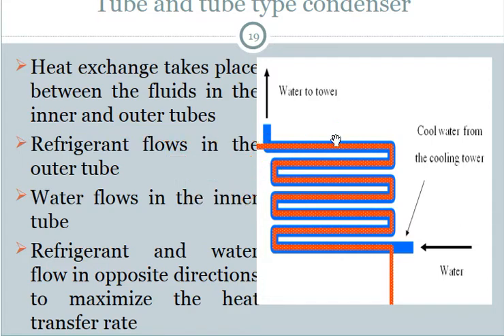The tube-in-tube type condenser follows the same spiral pattern for both the tube and shell. As seen in the figure, the red tube carries the refrigerant and the blue tube carries the water. Heat exchange takes place between the fluid in the inner and outer tubes. The refrigerant flows in the outer tube and water flows in the inner tube, in opposite directions, to maximize heat transfer.